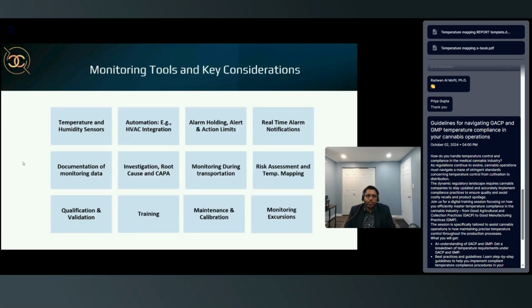Usually when we do the training, we go through the SOP management and a general overview of the system, but we do not discuss who is going to handle what if a breach is happening, and in what cases, what level of enforcement you want to take. Are you going to prioritize that over anything else you have going on? Or will it not be considered a priority if your humidity reaches 60% to 90% and stays there for 5 hours? I've seen very often that temperature and humidity monitoring are not given a very high priority, especially in the cultivation phase. And what I see is that the effect goes into the GMP also.